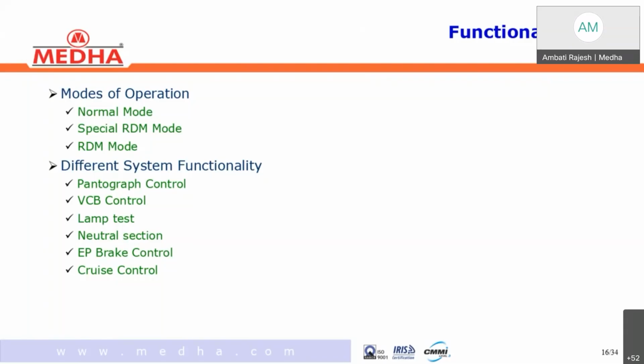In general, it should not be a standard practice. We should operate at 250, but even if operated at 100 meters or 200 meters, soon after the loss of OHE supply the system automatically starts the neutral section logic, and after OHE is established again, the system closes the VCB of the first DMC. The same logic continues for the other DMCs placed in the same rake. Automatically it will enter the neutral section logic.